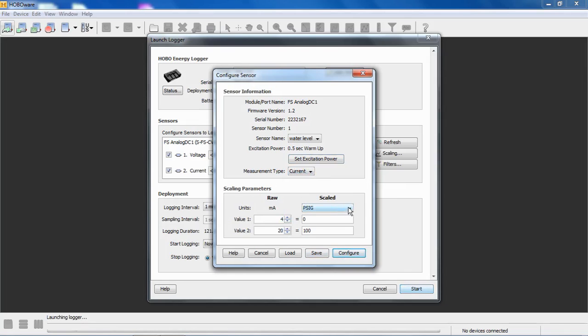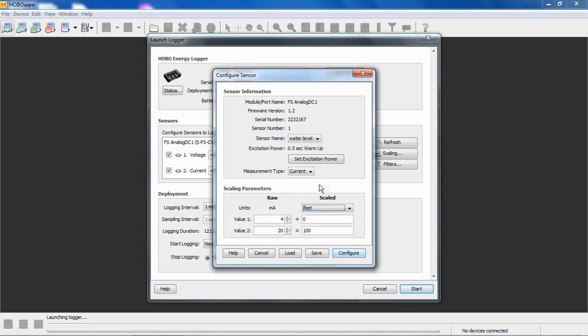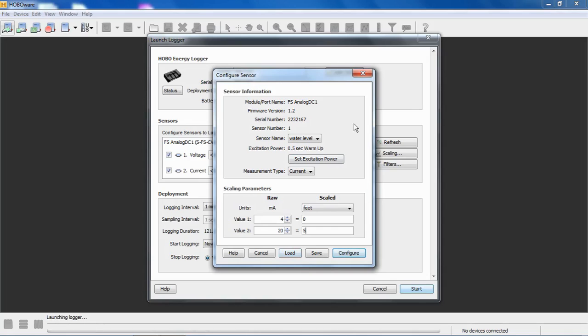So we know it outputs at 4 milliamps at 0%, 20 milliamps at 100% output. Under scaled, we want to put in how this device is scaled for this water level sensor. It outputs its signal that represents feet of water. So we're going to say feet, and this particular device, it's 0 to 5 feet of water level. So this is what we're saying is at 0 feet of water pressure or water level, we output a 4 milliamp signal. And at 5 foot, we output a 20 milliamp signal. So we have this module configured to measure water level. It will power that sensor. It will wake up a half a second before it takes a measurement, power up that sensor, allow it to stabilize, and then turn off until the next logging interval. It's important with excitation power and warm-up to make sure you have a long enough warm-up period to allow that sensor to stabilize. And it really is dependent on the manufacturer's recommendation as to how long you want that excitation warm-up time to be.